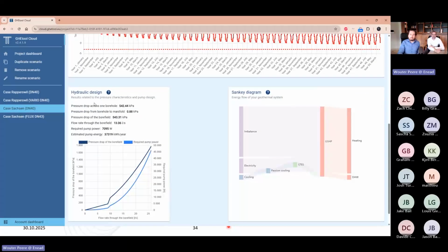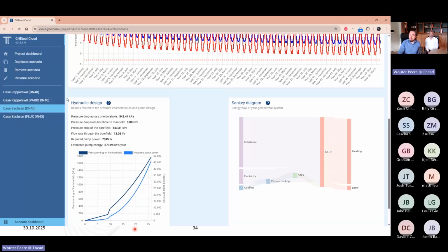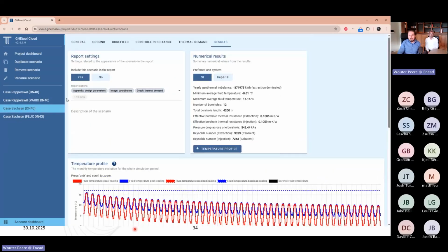If we then go towards the hydraulic design at the bottom, you see here that for the design flow rate, we have an estimated pump energy consumption of 37 megawatt hours per year of electricity usage. It's a deep borehole, quite a lot of flow, quite a high pressure drop and pump energy as well.